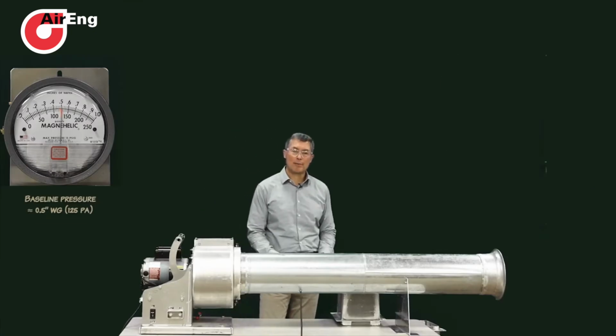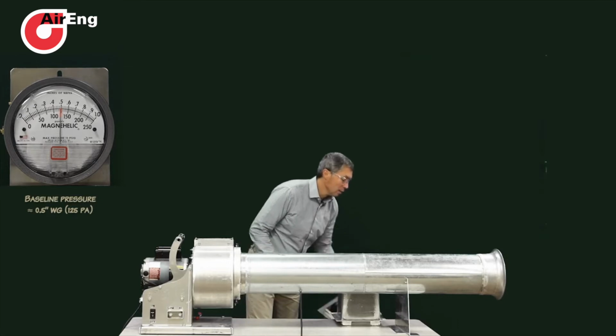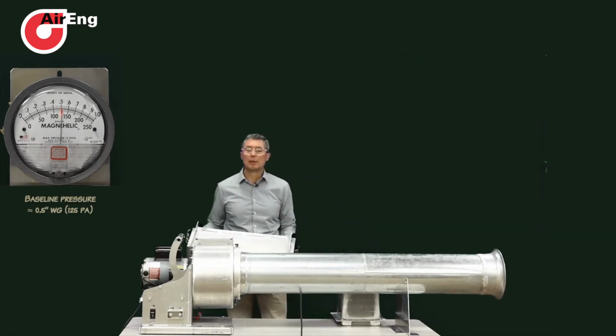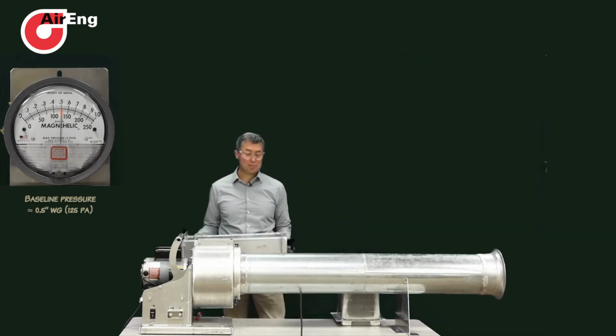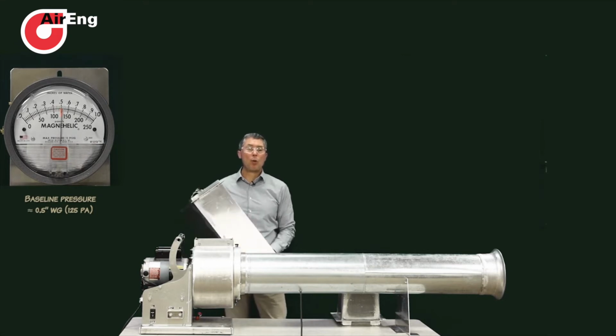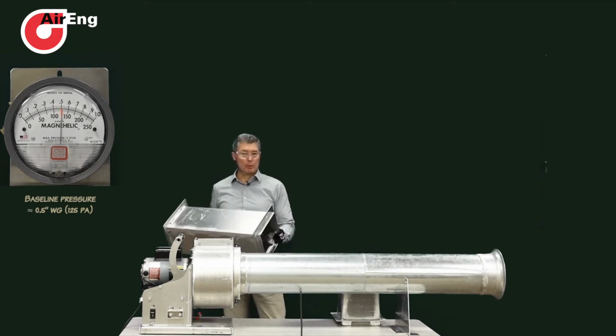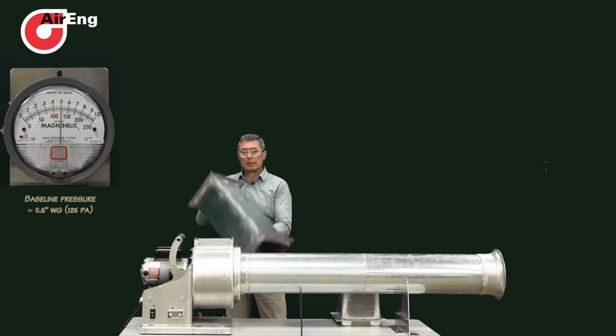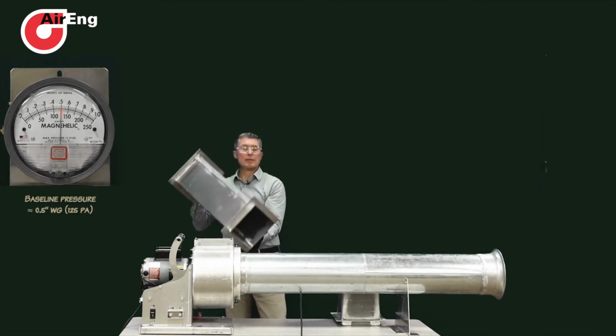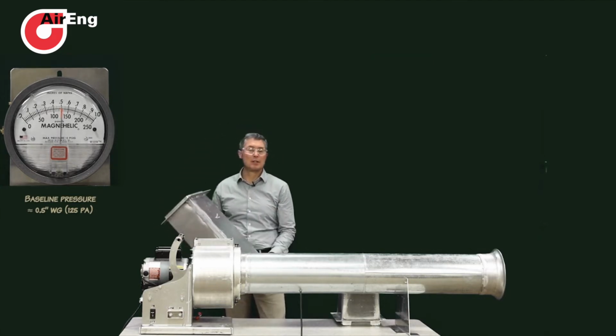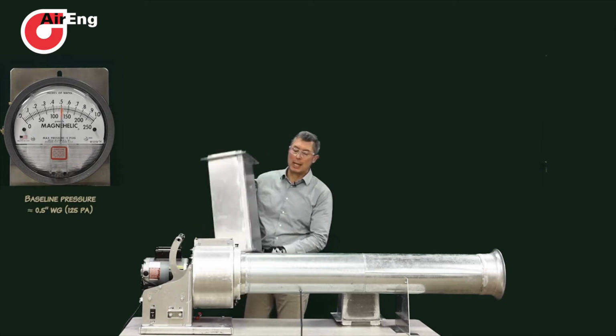To straighten out that velocity profile or get some static pressure regain, SMACNA, AMCA, most industry standards require or request a straight run of ductwork. And looking at the straight run of ductwork, there's nothing inside of it, just clean, open duct, nothing there to forcibly change the velocity profile.